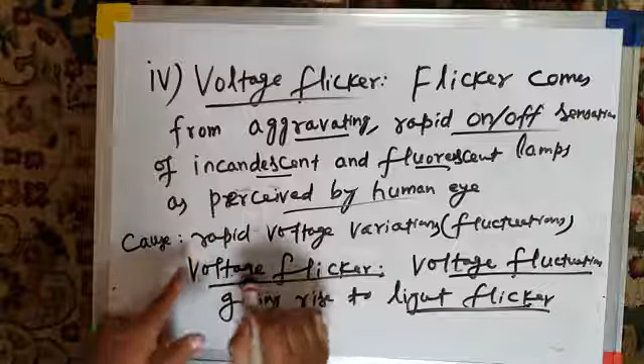Okay. Now this word voltage flicker is actually confusing. Actually, there is nothing like voltage flicker. Voltage flicker is actually voltage fluctuation. What does voltage flicker mean? It is a combination of two terms, voltage and flicker: voltage fluctuation giving rise to light flicker. Whenever there are rapid variations in the voltage, that is voltage fluctuations, what will they result in? They will result in light flicker. So voltage fluctuations giving rise to light flicker is what we call voltage flicker. So you should not get confused. Voltage fluctuation means rapid variations in the voltage. Voltage flicker means flickering due to voltage fluctuations.